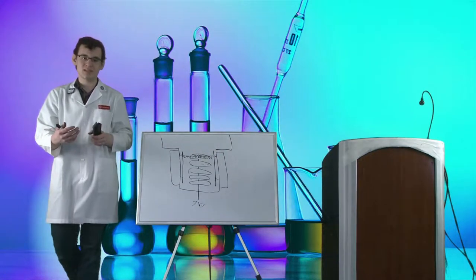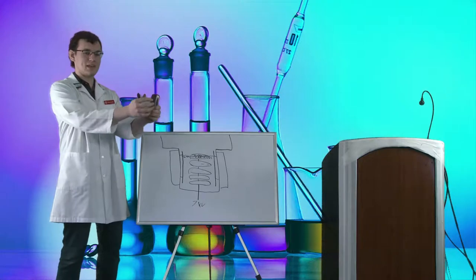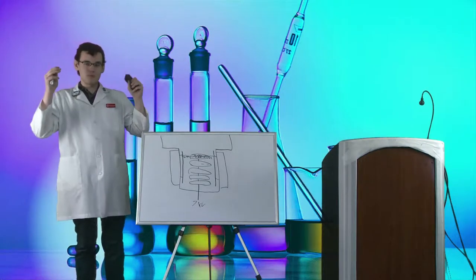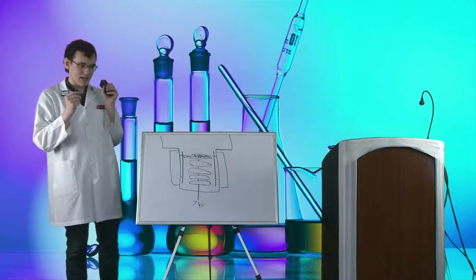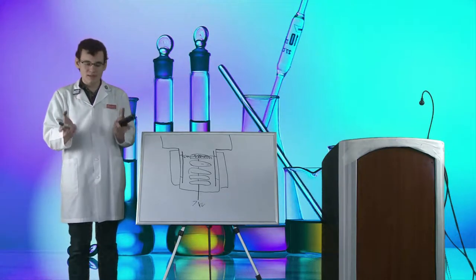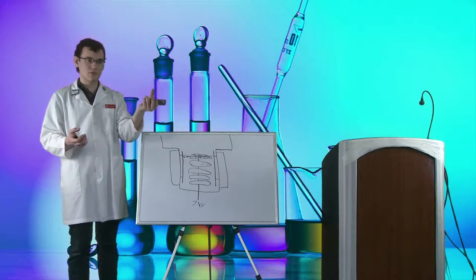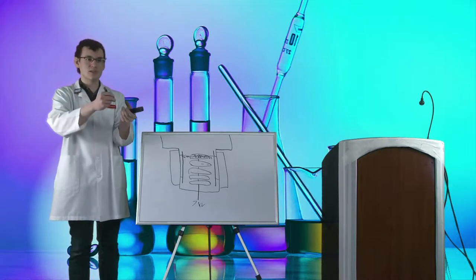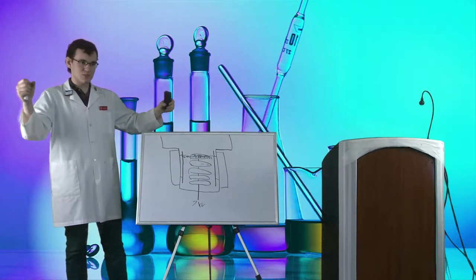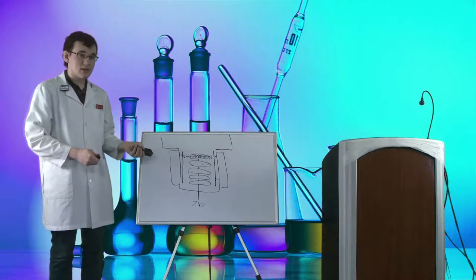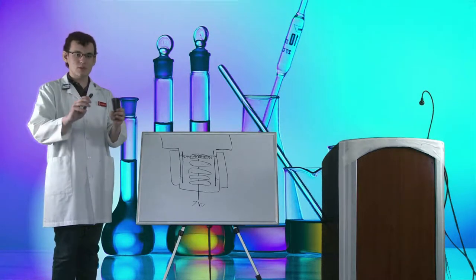It's a weird concept — a chunk of metal absorbing air molecules. That's why I stressed there are 14 orders of magnitude difference between atmospheric pressure and where these pumps run: it's hard to comprehend how little air there is. This would be like if you had a piece of metal rusting in a room — iron taking oxygen out of the air — except here it's actually removing so much material that it noticeably changes the pressure inside the vessel. That's called an ion getter pump, abbreviated IGP.